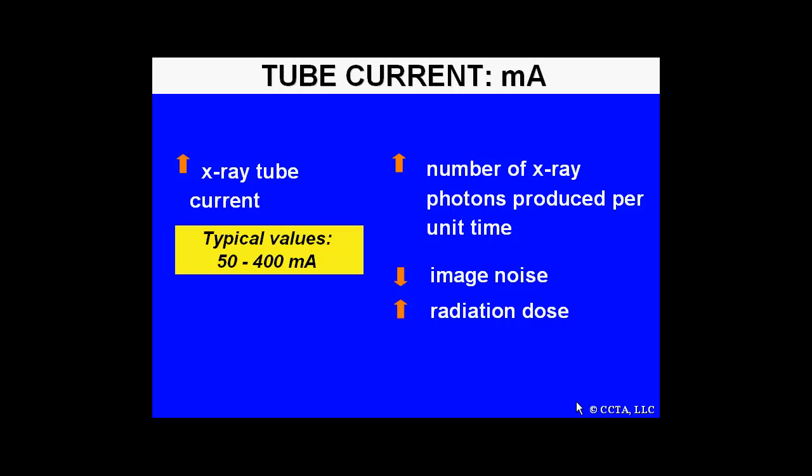The other parameter is the tube current, milliamperes or mA. Typical values range between 50 and 400. Increasing the x-ray tube current will increase the number of x-ray photons produced per unit time and decreases image noise, but also increases radiation dose.